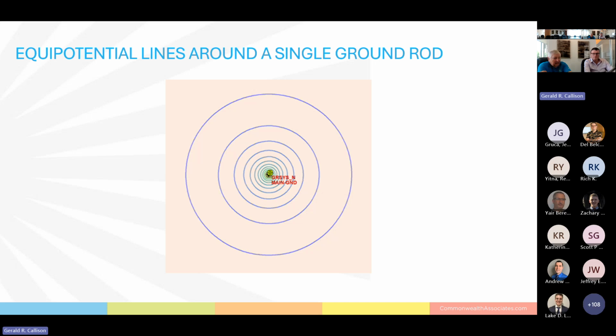So what does that look like? Well, if you take a ground rod, stick it in the ground, and energize that single ground rod, the blue lines represent the equal potential lines, and those lines drop off the potential with respect to remote Earth. The outermost potential line is lower, and the inner lines have a higher voltage. Each concentric circle represents a particular ground potential rise, and the further you get away from the ground rod, the lower the potential is.